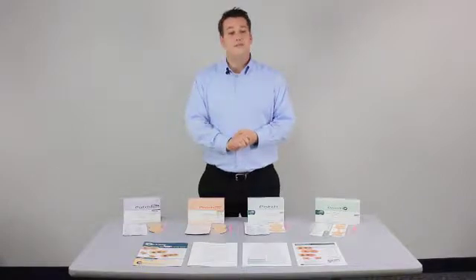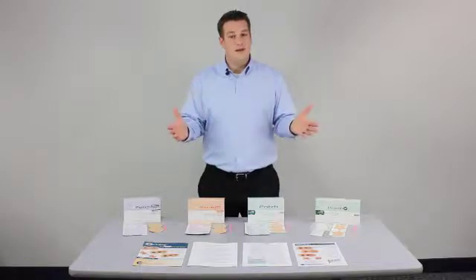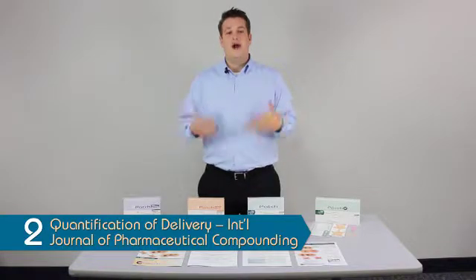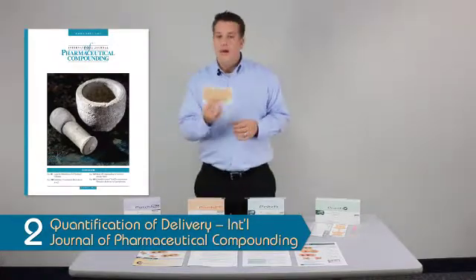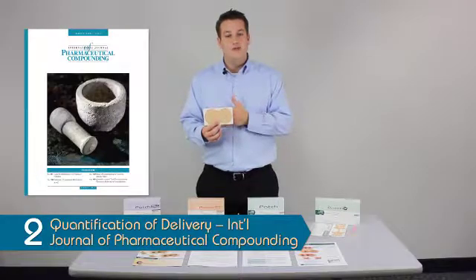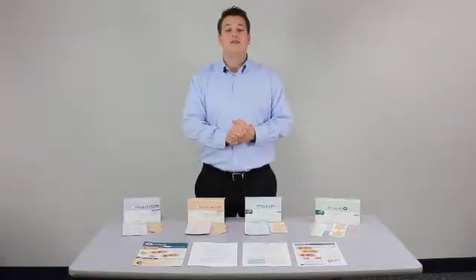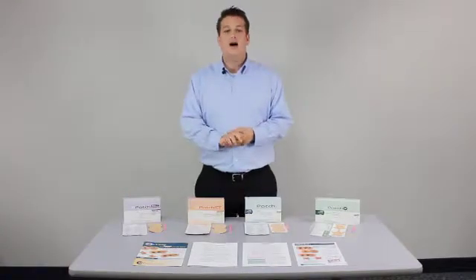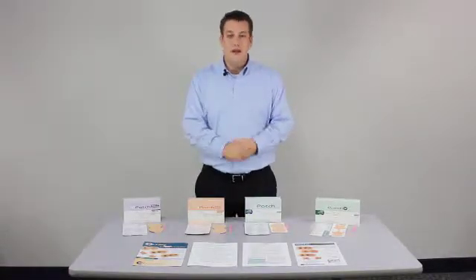The second part of that study shows it doesn't matter if you're using high current or low current — iontophoresis will only go so deep, which is about one to two centimeters into the tissue. The second peer-reviewed published study quantifies how much drug we are delivering in one patch, specifically an 80 milliamp minute patch. One 80 milliamp minute patch is going to deliver right around 1.2 to 1.4 milligrams of drug. That's why you see six patches in a box — six patches is equivalent to one injection. This is true for all of our products except for our extra strength product, where only four patches gets you the same amount of drug delivered as an injection.